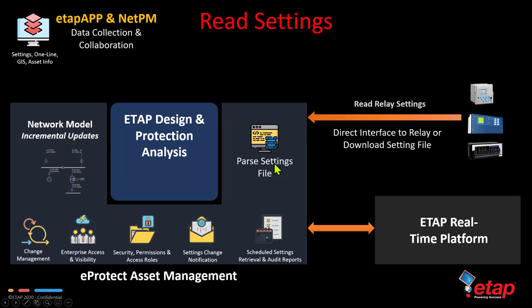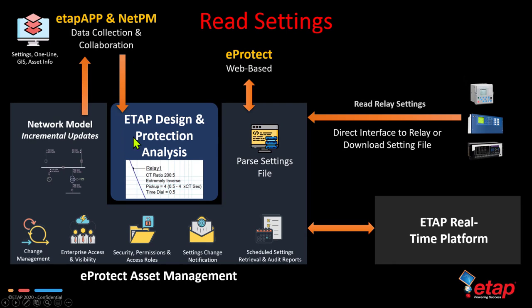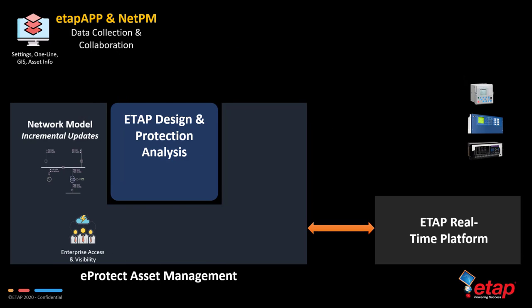The setting file is then parsed and then essentially is visualized inside the eProtect web-based interface. The setting file is also stored in the database and version controlled. The setting file is then broadcasted through NetPM and then downloaded into ETAP design and protection analysis software, where you can essentially visualize the TCC or the distance characteristic for the relay. A settings change notification may also be triggered if the ETAP coordination program has a setting different than what was just retrieved from that relay.